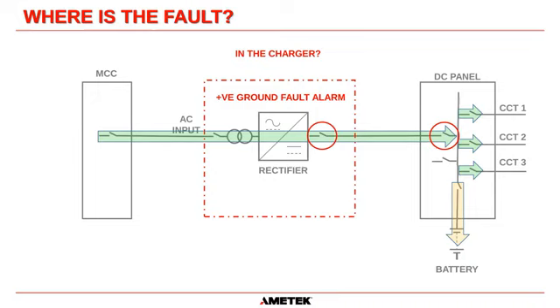And that is what's going to happen in the majority of cases. Okay, you're going to open this output breaker and the ground fault will clear. So if the ground fault clears, then what we can do is now we can test the cable between the charger and the DC panel. Hopefully your system has been installed like this.